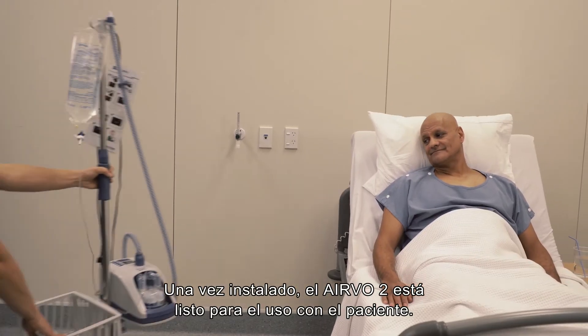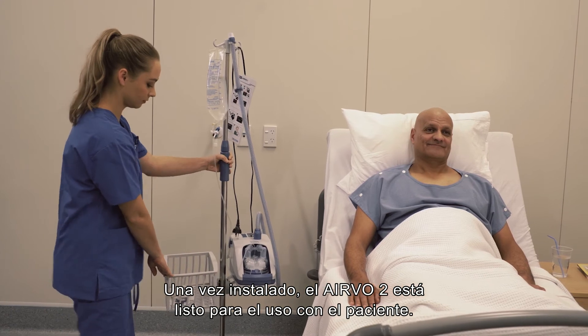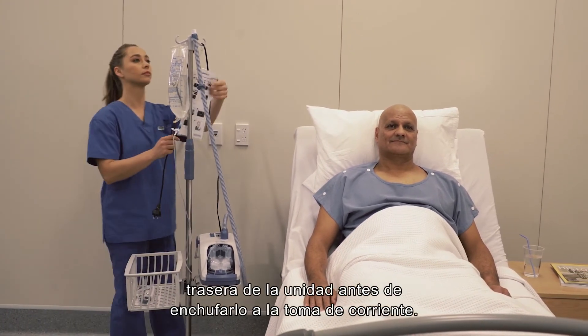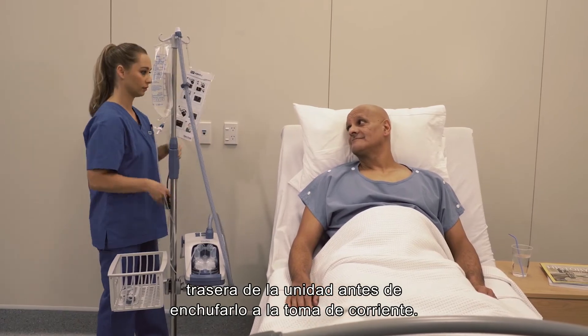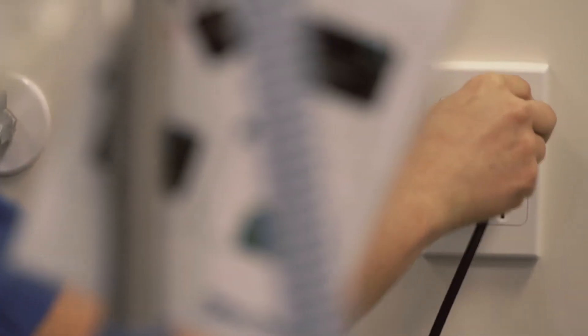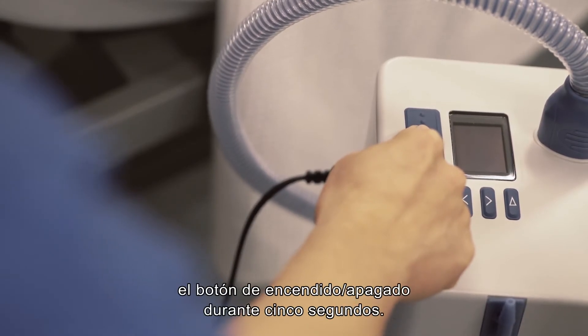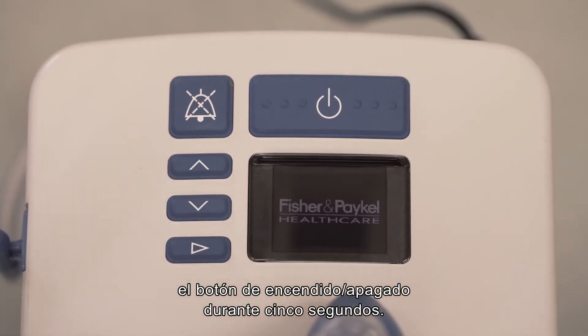With setup complete, the AIRVO 2 is now ready for your patient. The AIRVO 2's power cord should be well secured to the rear of the unit before plugging into the mains utility power socket. Switch on the AIRVO 2 by pressing and holding the on-off button for 5 seconds.